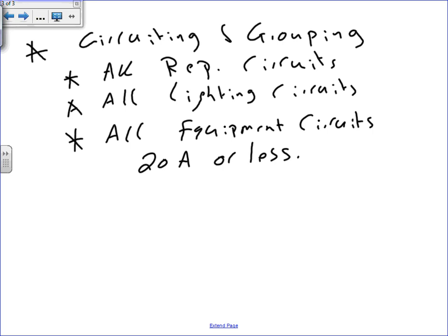For example, I have a printer there. I need a branch circuit dedicated for this printer. That needs a 20 amp circuit, two conductors, number 12. Should I send a conduit directly to this, or should I grab these two conductors and put them in a conduit with the receptacle and the lighting panel and the lighting? Yes, group them together in the same conduit, if you can. Does that make sense? Anything higher than 20 amps, mechanical equipment, in my humble opinion, put a dedicated conduit to that load. So 20 amp or less, or number 12 conductors. If it's wired with number 12 conductors, group it.